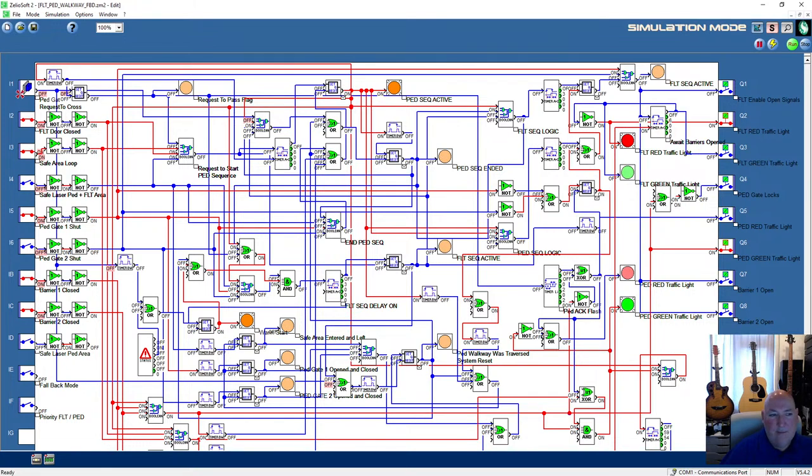So if they keep pressing another sequence, what happens? It resets the timer, carries on going. Starts over. That's good. As long as the trail of people crossing keep pressing the button, it'll hold off that timer. But what we don't want is the trail of people suddenly stopping. It needs to hold the timer off, or stop it switching at least.